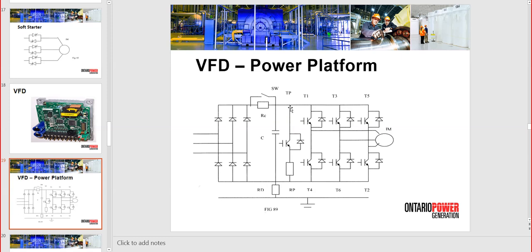What's happening with this leg? Once the DC bus increases to 110%, because the motor became a generator, you are slowing down and you release power from the electrical machine which became a generator. If it's a large inertia load, that will take quite a while to stop. The power goes back through the diodes into the capacitor bank. So the capacitor bank will increase the voltage because the power has nowhere to go, and you need to dissipate that extra power by chopping this on and off resistor that is external, a power resistor on a heatsink, and that way you get rid of the extra power and the voltage goes down. If you don't manage to do that, the drive will protect itself, and you will have a message of DC bus over voltage, and it will stop.